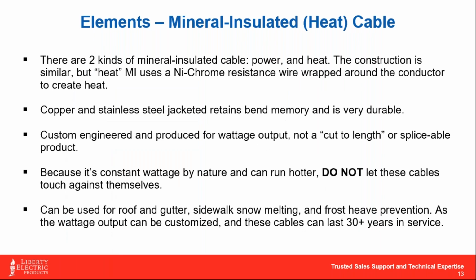Then we've got mineral insulated cables. Some of you, especially the electrical folks, might be familiar with these. Mineral insulated cable comes in two forms: one is a power cable, one is a heat cable. We see the power cable side when we're doing things like fire pump protection, to ensure the fire pump can continue working in fire rated conditions at 1,000 degrees. They're built very similarly, only one has a resistance wire and one does not.